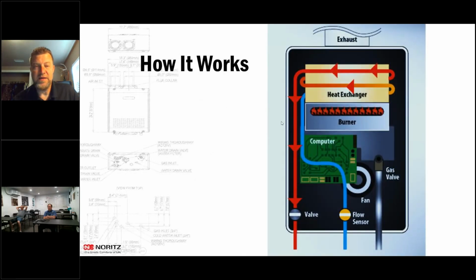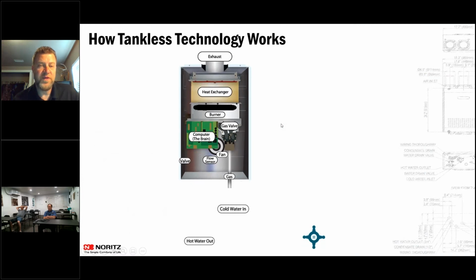So tankless water heaters, basically, the biggest question we always get is how does it work? With a tankless water heater, you do have the exhaust coming out of the top. There's a heat exchanger inside, just basically small little tubes that the water's running back and forth through. With non-condensing, there's only one heat exchanger. With condensing units, there's two heat exchangers, which we'll cover here in a little bit. Every tankless water heater has a burner, whether it's an upward burn or downward burn. All the tankless water heaters have to be ultra low NOx in the United States, especially here in Utah. We have to be ultra low NOx, 20 parts per million or less, to meet the current codes that are there.